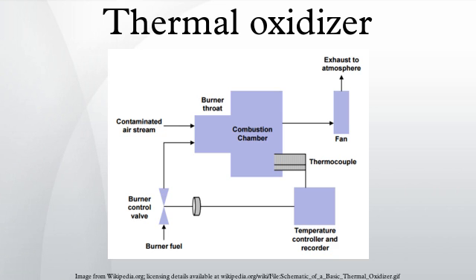A less commonly used thermal oxidizer technology is a thermal recuperative oxidizer. Thermal recuperative oxidizers have a primary and or secondary heat exchanger within the system. A primary heat exchanger preheats the incoming dirty air by recuperating heat from the exiting clean air. This is done by a shell and tube heat exchanger or a plate heat exchanger.